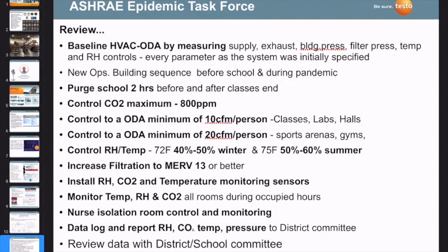So number one, they want all school systems to be baseline measured. That means, again, going back and measuring the basics: your supply and exhaust CFMs, the pressure differential across all the filters in the system, relative humidity and temperature set points measured in the classrooms, measurement of outside airflow, if any, and how does that correlate or compare to the original set points that were established when the system was installed, either when the building was built or when that system was replaced.